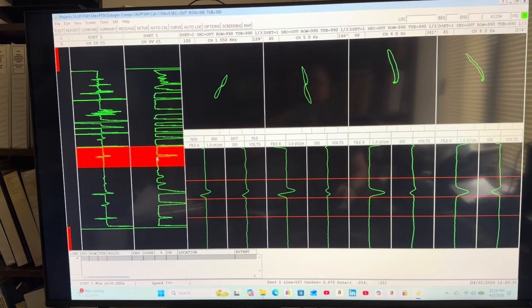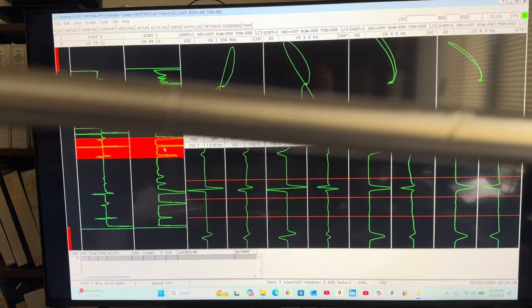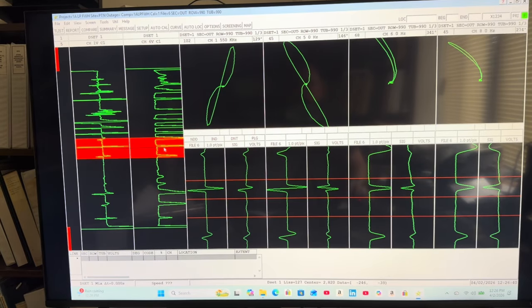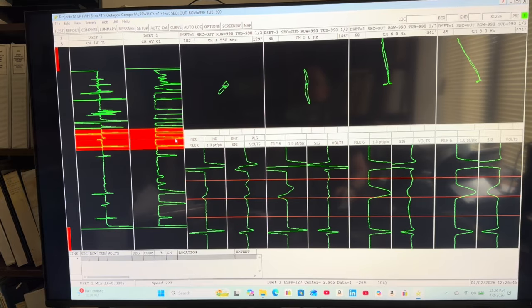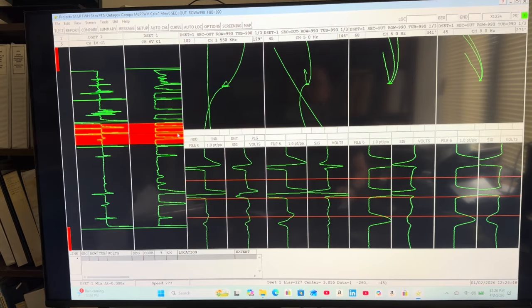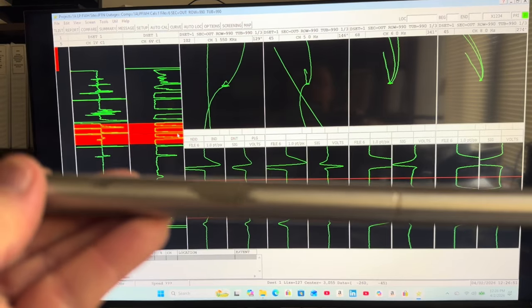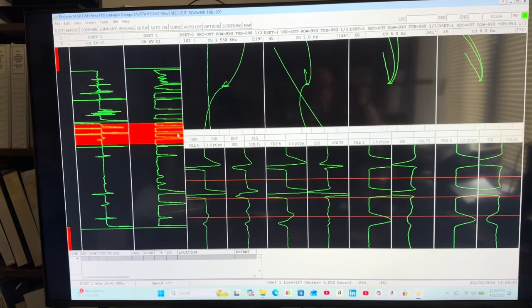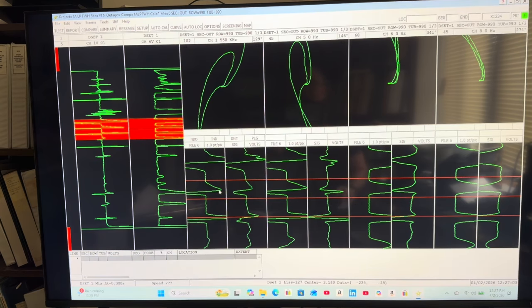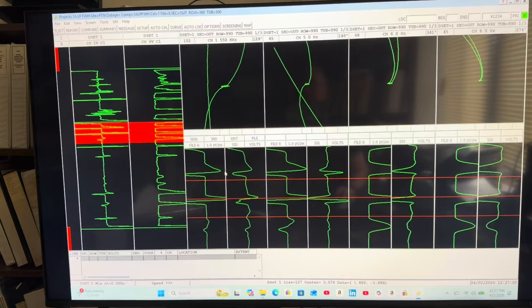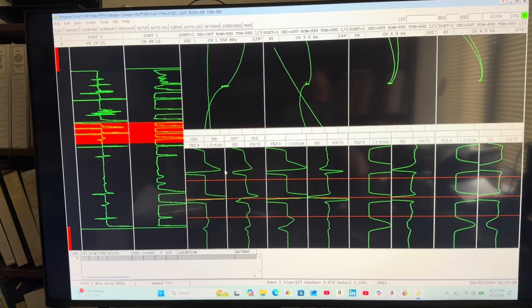Then, the next thing is I think this diagonal hacksaw cut. No, that's not it. The hacksaw cut's going to be wider. Maybe that's the hacksaw cut right there. And then I've got a circumferentially oriented hacksaw cut, fairly deep. So notice how, even though it's circumferentially oriented, you can get these huge signals. That's because they have some width to them, or to the bobbin coil, it's got some axial extent.